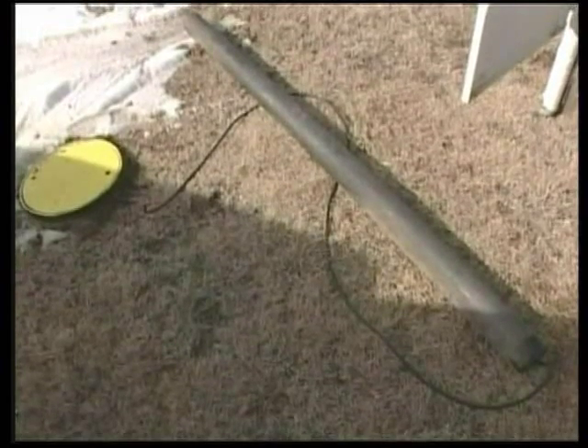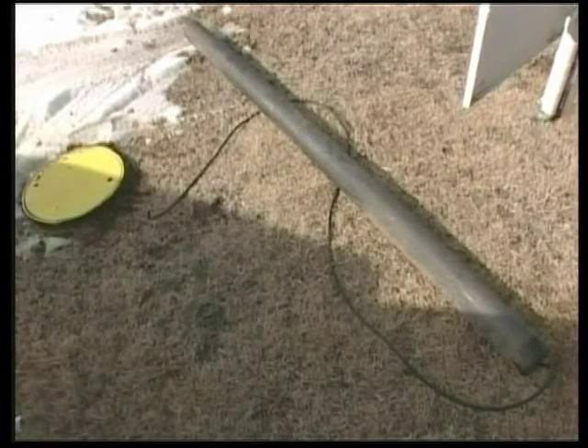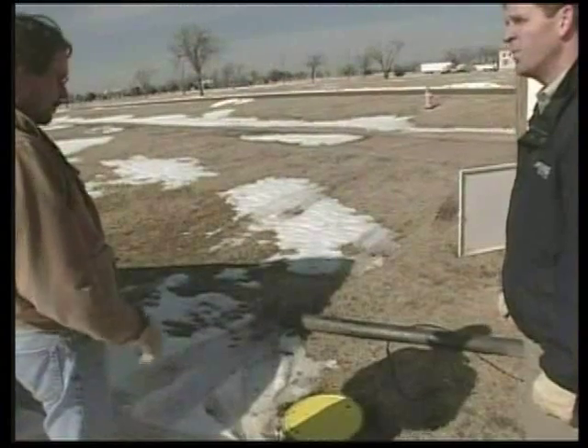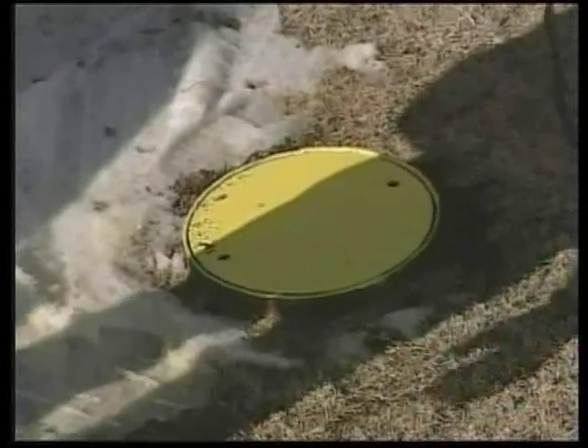You also talked about the impressed current system. It works a little differently than the magnesium anodes — you have graphite anodes instead of magnesium. What we do is drill a hole down to where we want good formation where the current will flow through the ground well. In this case, it's 450 feet deep.